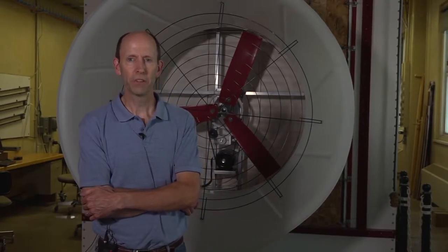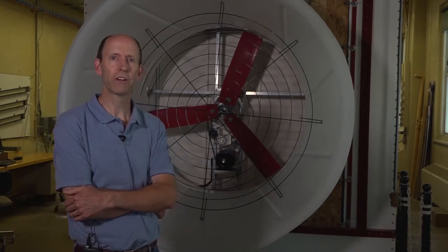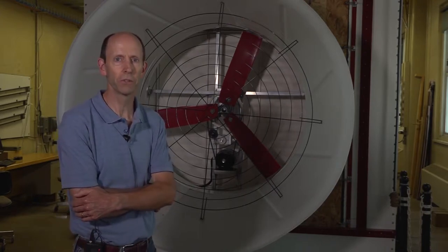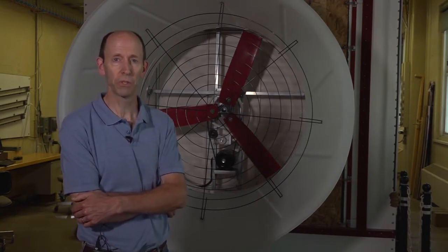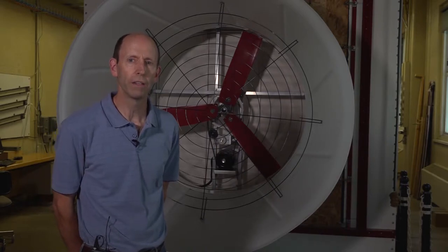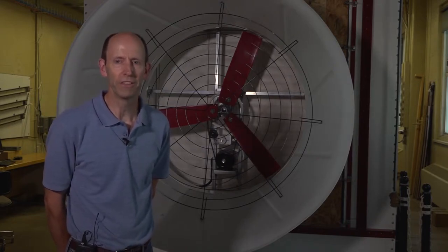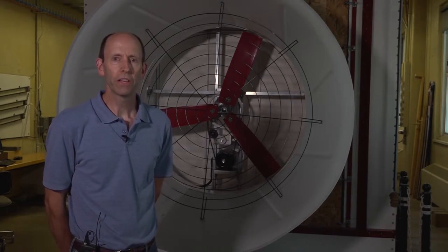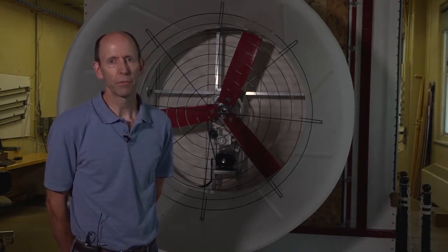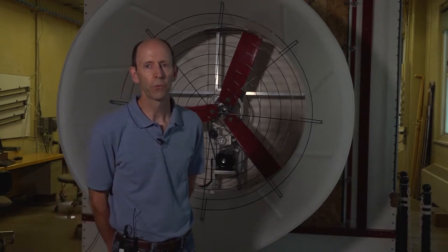We're at the BESS Lab at the University of Illinois, and we're in the fan testing business here. Behind me, we have one fan on our chamber. So primarily the main focus here is we're looking at two parameters. And that is air flow, which is measured in cubic feet per minute or CFM, and then also ventilation efficiency ratio, which is CFM per watt. You can think of CFM per watt kind of like miles per gallon on your car. So it's how much do you get out for what you put in.